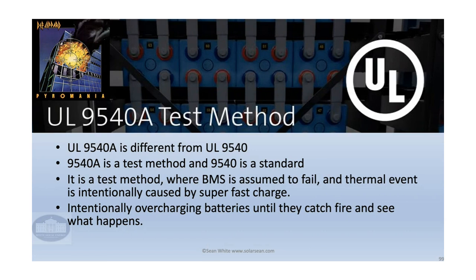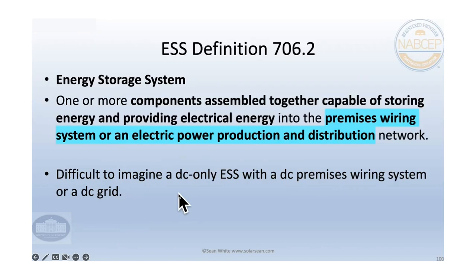You can put two right next to each other, right up against each other if you install them that certain way. And that's because Tesla went through the 9540A test with two next to each other that way. Otherwise, you wouldn't have to follow the 9540A, but you would have to keep the batteries 3 feet apart. And so we're going to look at all that kind of stuff coming up. We need to move fast forward because we only have so much time for all that.